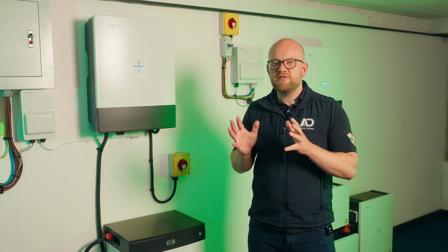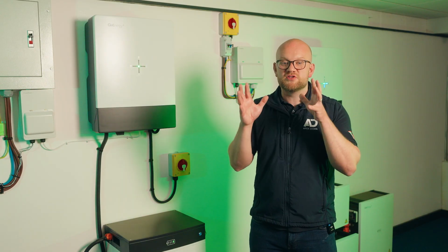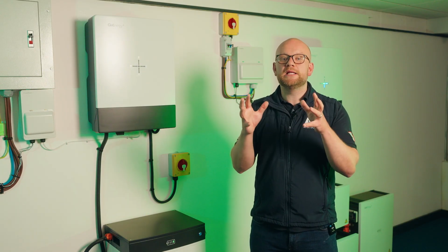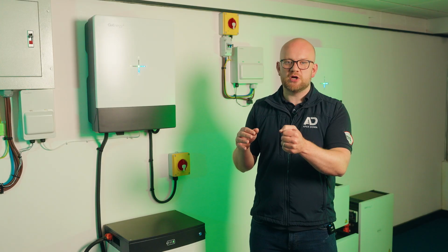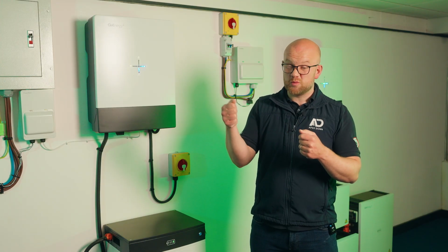Now, if you're on a three-phase system and you're lucky enough to have something like a swimming pool or a big load, you would want a manual changeover switch because you'd essentially need to turn your swimming pool pumps off in the event of a whole house cutout, and then you would want a manual changeover. If your loads are a lot lower, so below the theoretical floor limit of your inverter, then an automatic changeover switch would do.